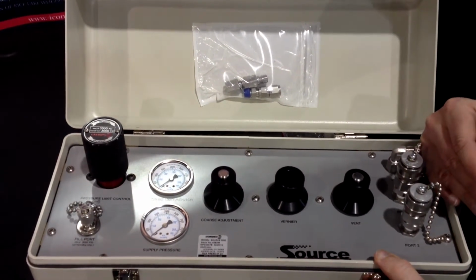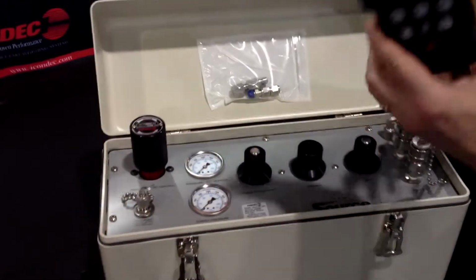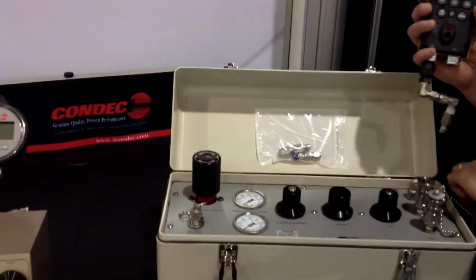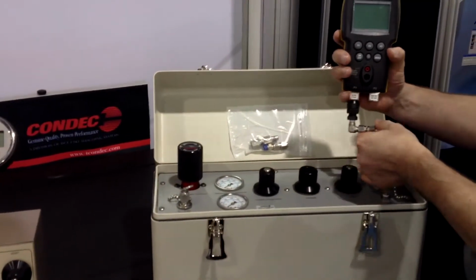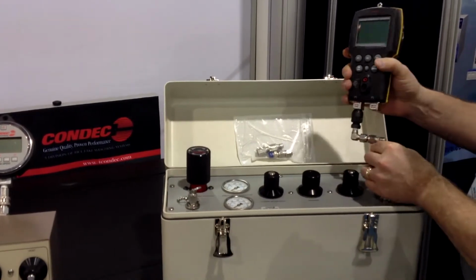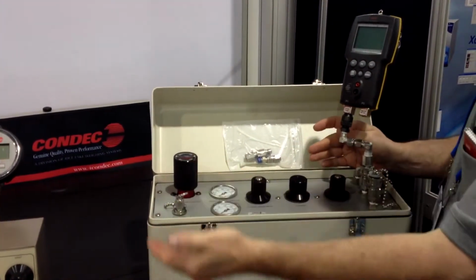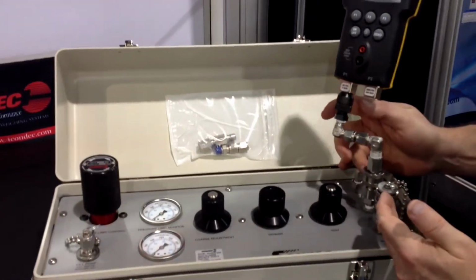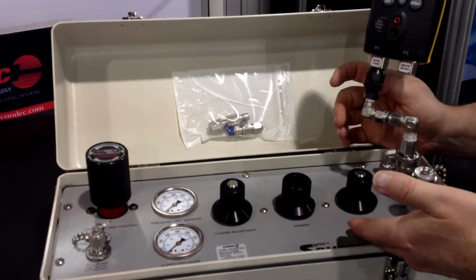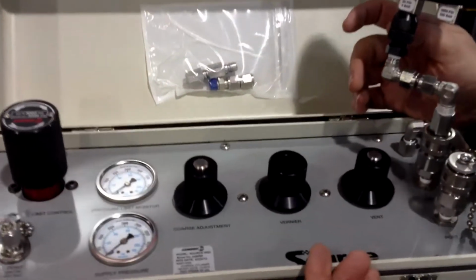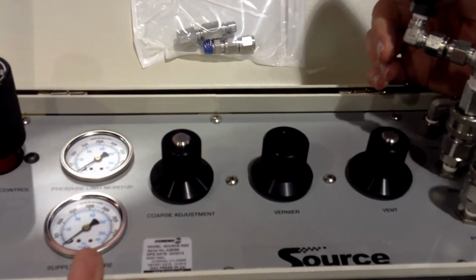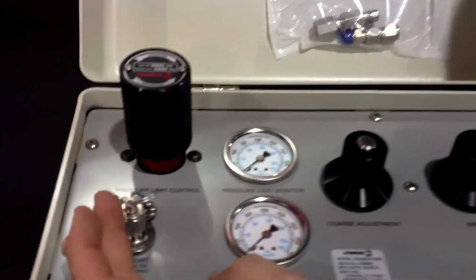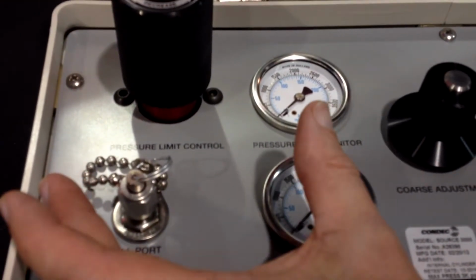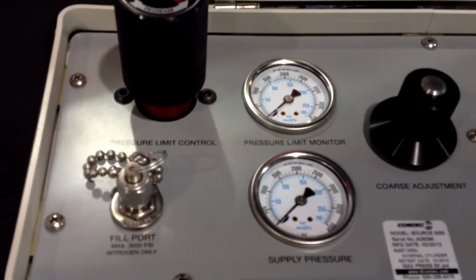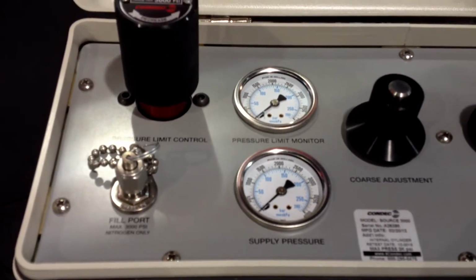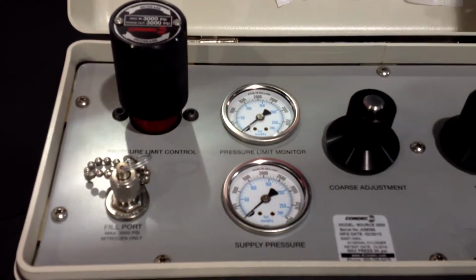To get yourself set up, you would have a handheld or a gauge that you would use as your calibration device. You're going to have a regulator which regulates the output pressure going to your test ports. You're going to have an Orion valve system with your coarse adjustment, your vernier, and your vent valve. You'll have two analog gauges. One is tied into your regulator, showing your supply pressure, and the other is your pressure limit monitor gauge, which shows the pressure coming from the cylinder and going to the device under test. Again, that's for the protection side of things.